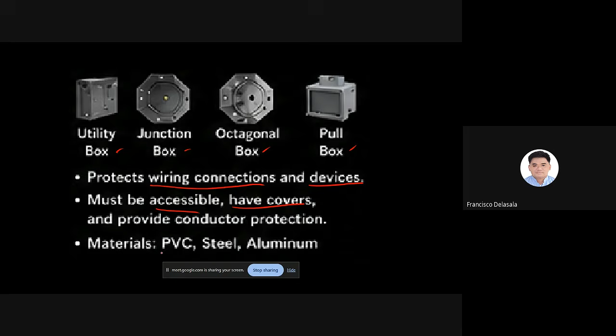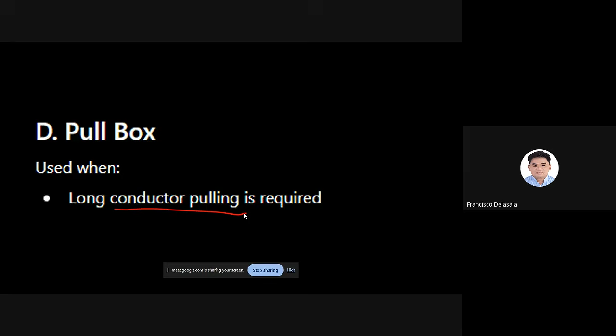Doon po natin i-indicate yung ating switches and receptacles. Junction box is where we do our splicing or jointing of wires. The octagonal box is for lighting outlets, yung mga lamp holder natin. Pull box is used when long conductor pulling is required, so this is to give space para madali nating mahila yung ating mga conductors.